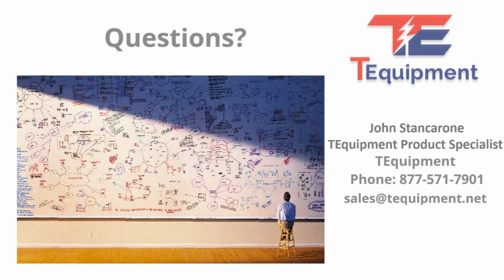I see. Now, another question was, can insulation resistance test be used to find a ground fault? So I guess that's the purpose of doing an insulation resistance test, to determine if you have a grounded system where it should not be. So with the insulation test, you determine that there's a ground fault. And yes, you can go and do troubleshooting. You can divide and test one section of the system and find that it is good. Then you test the other section, you find the problem there. So you keep dividing it until you find the specific spot.